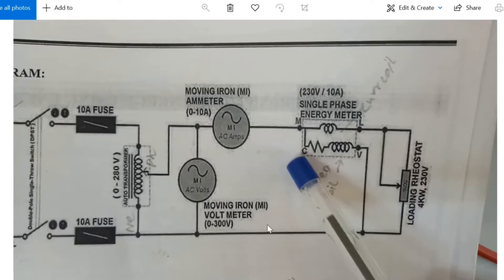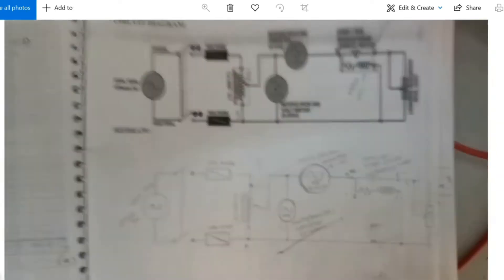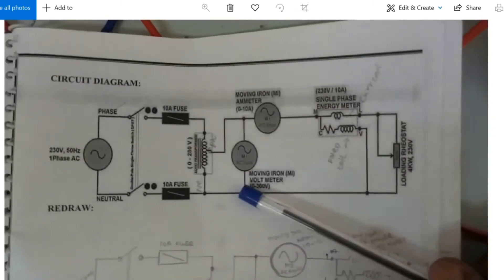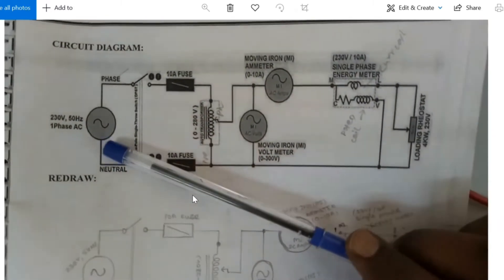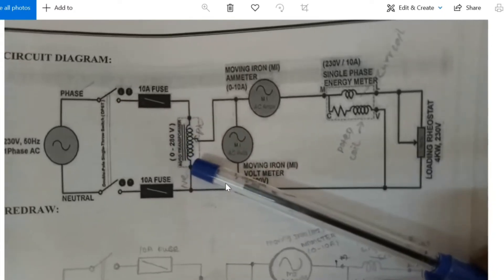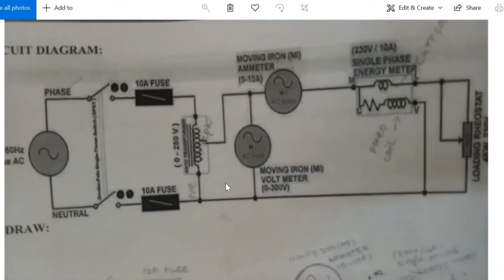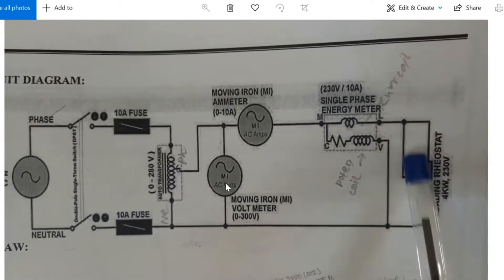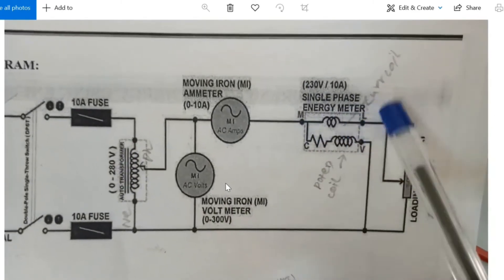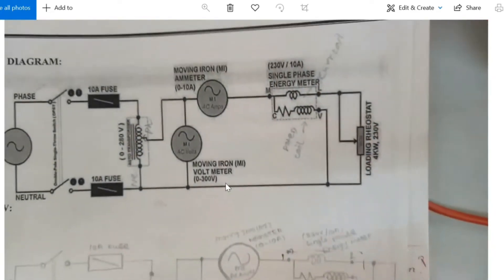Looking at the circuit diagram: the energy meter has M, L, C, V coils. Supply is given to the auto transformer via fuses. From the auto transformer, one end goes to the ammeter (moving iron type) and another to the voltmeter. The ammeter is connected to M of the energy meter, then energy meter L2 goes to the load. The load connects back to the auto transformer. M and C are short-circuited, and L2 load and V2 return to the neutral point.